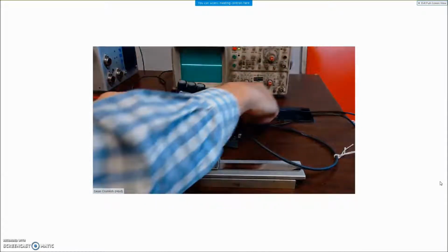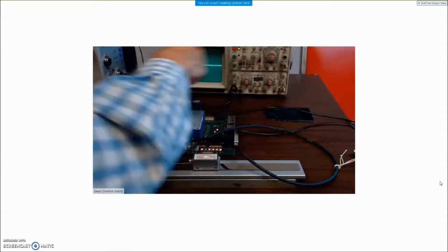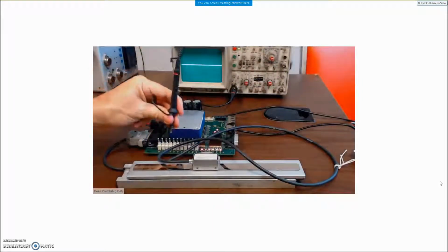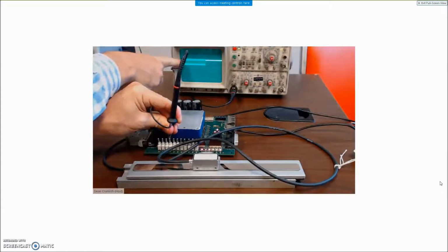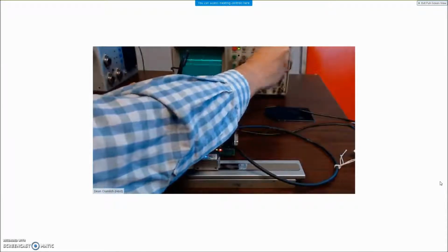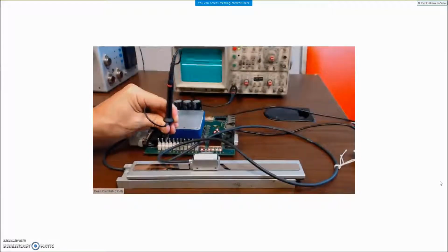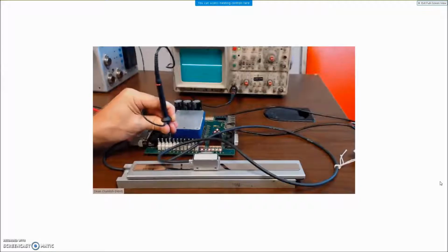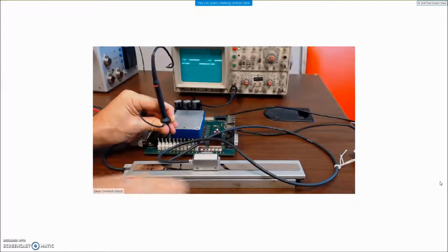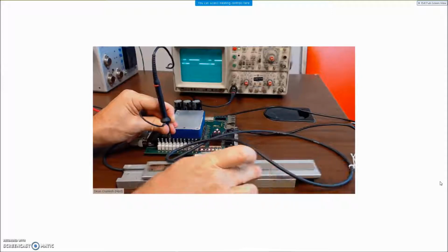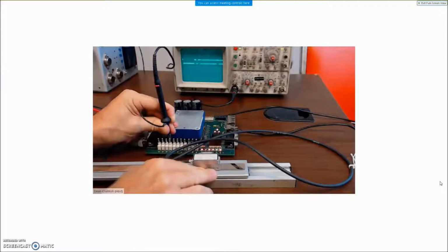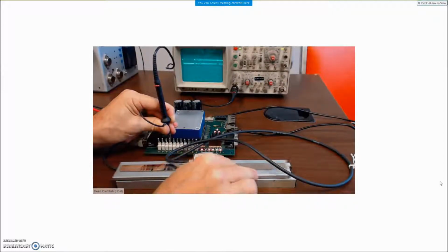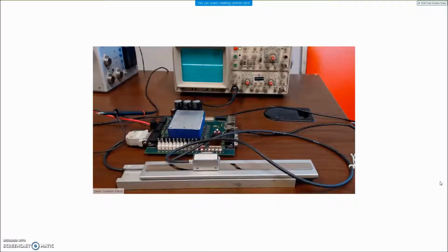If we're having any difficulty getting a signal, you can check the clock from the drive. So looking on the X, you'll see a burst of megahertz frequencies, which you can determine if there's a clock signal. And then if there's a clock going out, you should get data coming back. So as the position varies, you can see the count change. So there's the count change based on position. So clock out, position brings back the data.